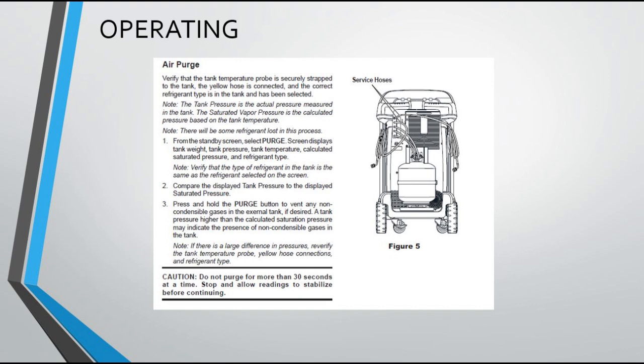Screen displays tank weight, tank pressure, tank temperature, calculated saturated pressure, and refrigerant type. Note: verify that the type of refrigerant in the tank is the same as the refrigerant selected on the screen. 2. Compare the displayed tank pressure to the displayed saturated pressure. 3. Press and hold the purge button to vent any non-condensable gases in the external tank, if desired. A tank pressure higher than the calculated saturation pressure may indicate the presence of non-condensable gases in the tank.